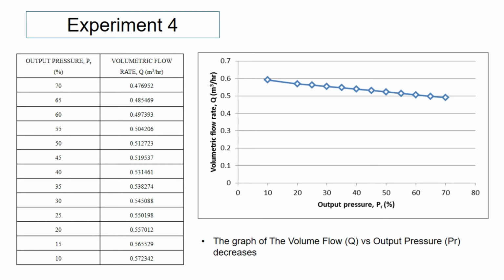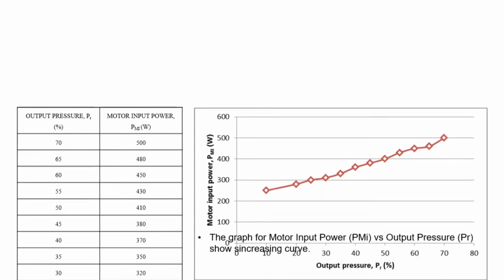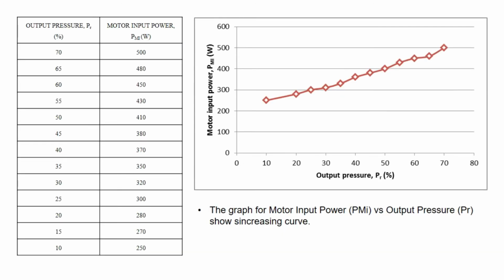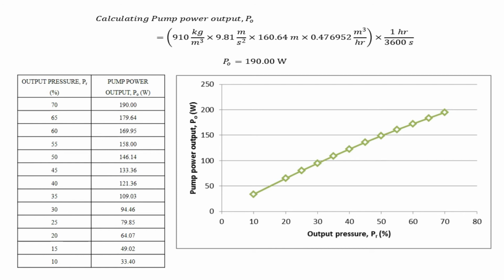In experiment 4, as shown in the table, as the output pressure decreases, the volumetric flow rate increases. Next, we have a table of output pressure and motor input power. As shown in the table, as the output pressure decreases, the motor input power decreases. In this experiment, we need to find the pump power output, PO. To find the pump power output, we use the equation as shown in the slide and substitute the volumetric flow rate into the equation.